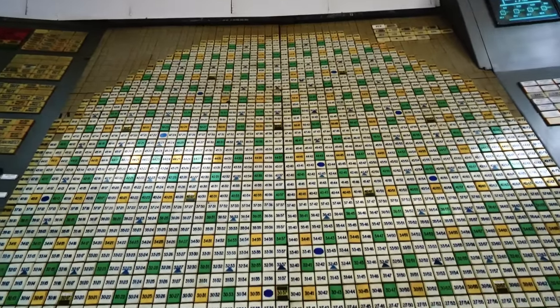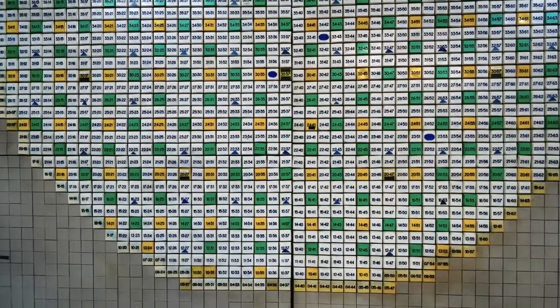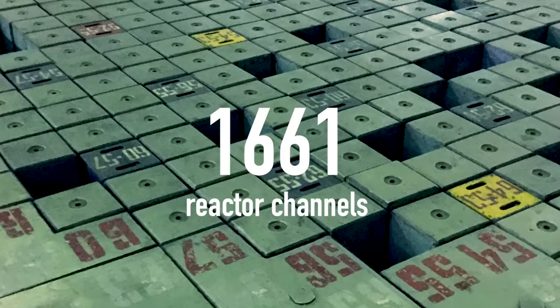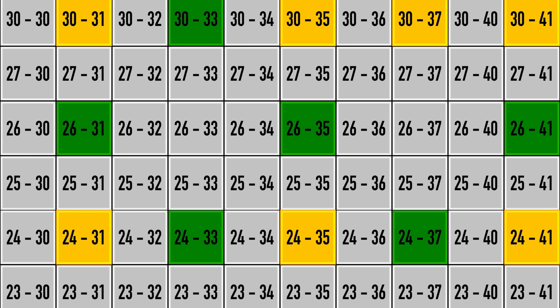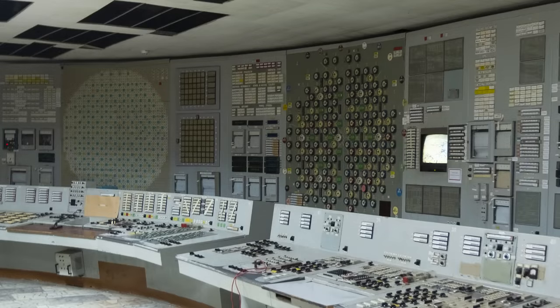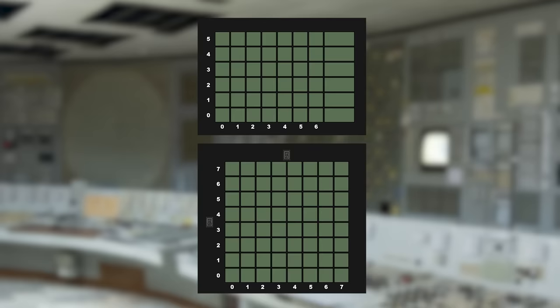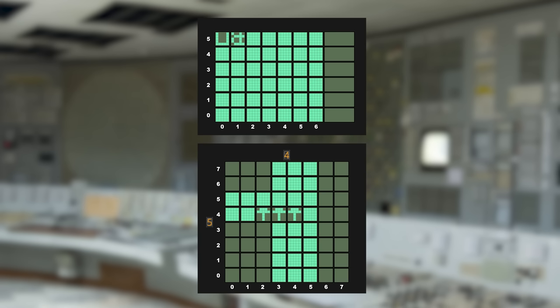These iconic mosaic displays are so-called Mnemonic Displays of Reactor Channels, or MTKs. Each square piece of this mosaic represents an individual channel — there are 1,661 of them in total. A special coordinate system using octal notation is used to identify each channel during reactor operation and fuel rod reloading. Specifically at Units 1 and 2 control rooms, you can also see Mnemonic Displays of Deviations, or MTO panels, which are connected to SKALA and provide real-time information about temperatures, pressures, flow rates, power levels, and so on.